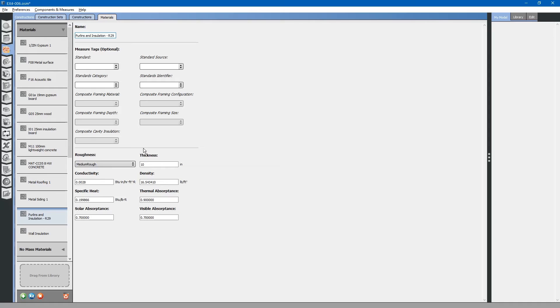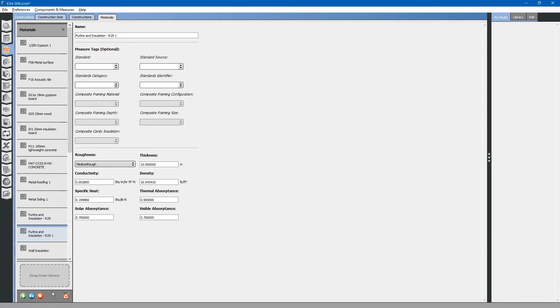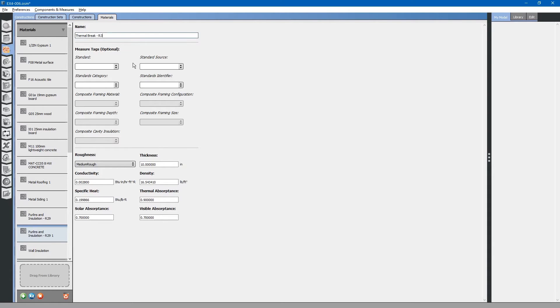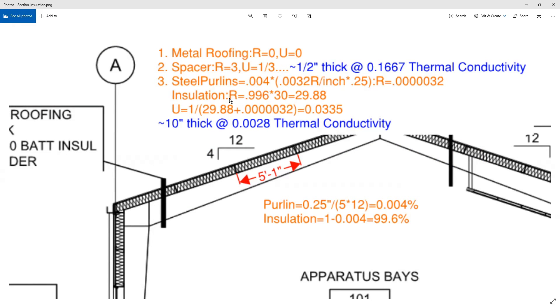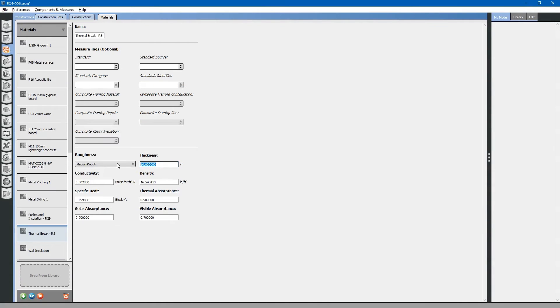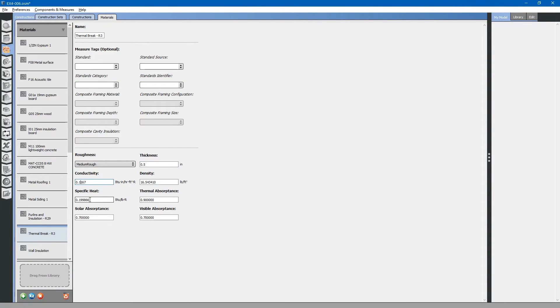Now we have edited that construction material. Next, we also have to create that thermal break. Let us duplicate this construction material. Select x2. We will call this thermal break R3. Looking at the thermal break, we have an R value of 3 which basically equates to a half inch thickness and 0.1667 thermal conductivity.